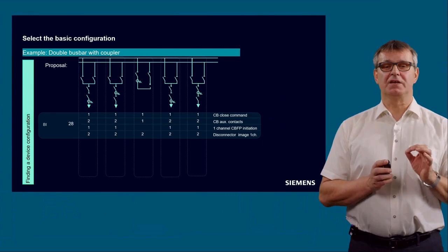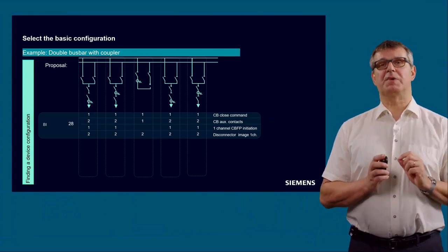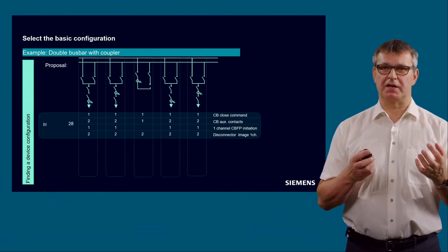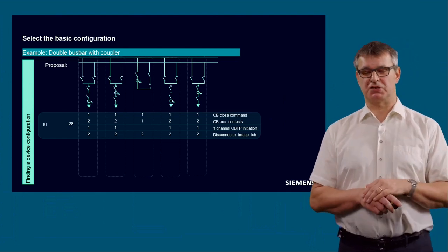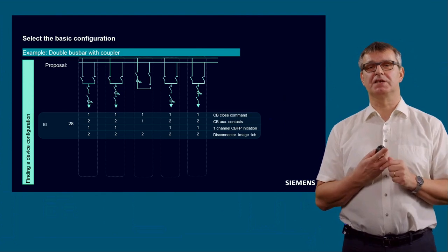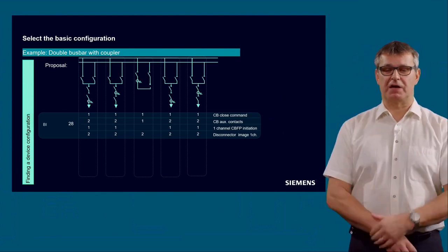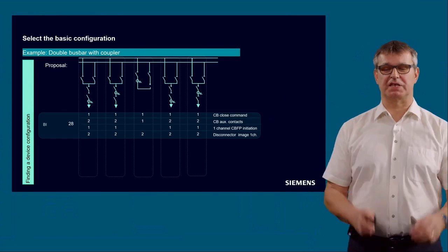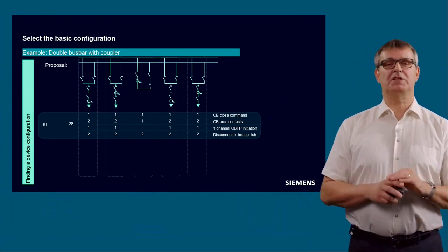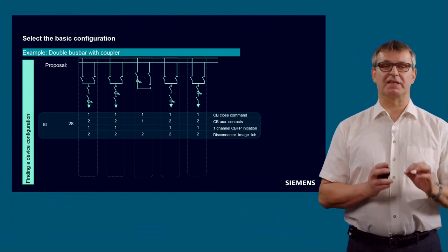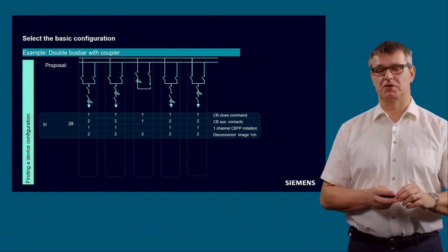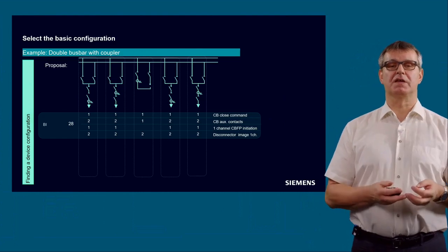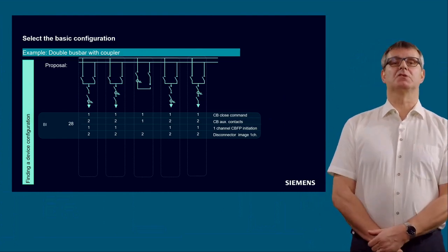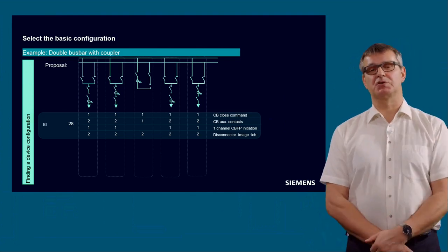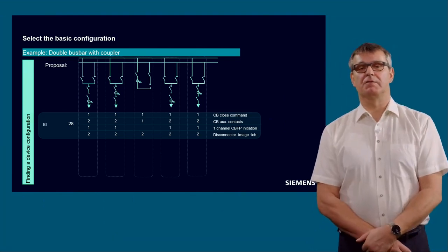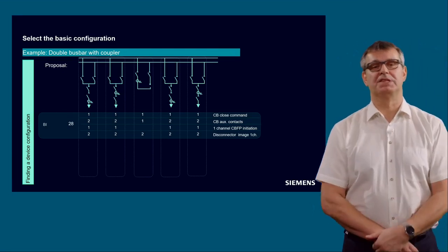So if there is any wrong triggering of the busbar protection, typically, as a product lifecycle manager for busbar protection, typically 1 or 2 times a year, there's a high upset in our organization about a wrong triggering of a busbar protection, and nearly every time the reason was that they forgot, they have end-fault protection, they have an external fault, they have an automatic reclosing, and they forgot to use the circuit breaker close command, and you have a wrong triggering of the busbar protection because the end-fault protection was deactivated too late because of the missing close command.